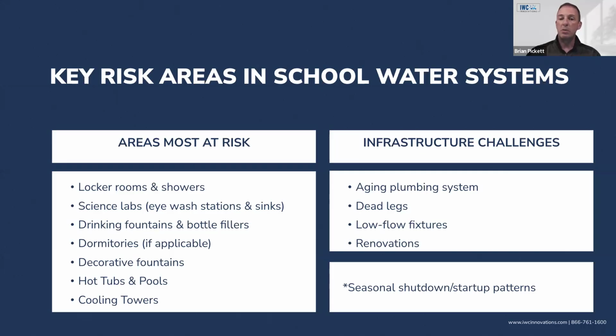And as a building goes through pressure changes throughout the day, and what I mean by that is water flow, people turning on and off faucets and fixtures, that changes the pressure within a pipe. And if the pressure goes low enough, that water that's sitting in that dead leg could actually flow back into the main header. And then as it repressurizes, pushes it throughout the building. So it could lead any type of bacteria that was in that dead leg to go further into the building. And then obviously seasonal shutdowns and startup procedures or patterns.